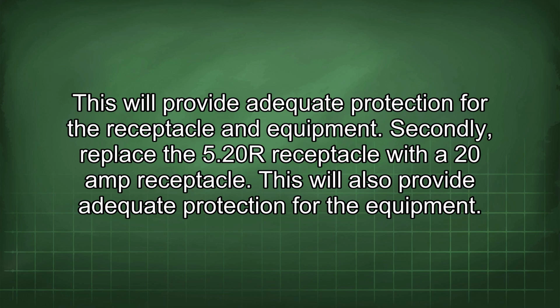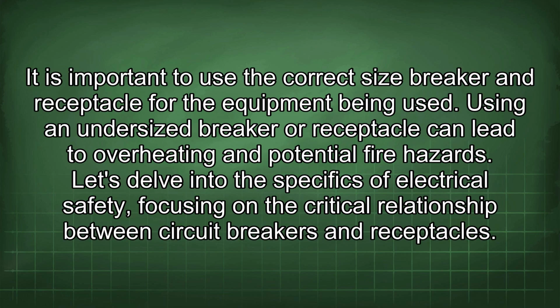Secondly, replace the 5.20R receptacle with a 20 amp receptacle. This will also provide adequate protection for the equipment. It is important to use the correct size breaker and receptacle for the equipment being used. Using an undersized breaker or receptacle can lead to overheating and potential fire hazards.